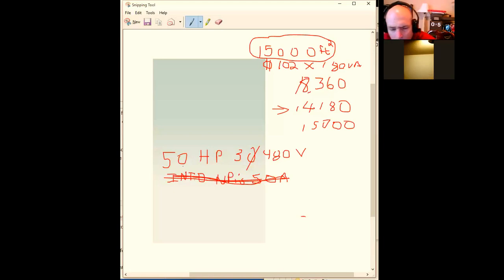Okay, what you got? I've got a fire pump motor that is a 50 horsepower, 480 volt, 3-phase motor used as a fire pump. And they're asking what size inverse time circuit breaker would you select to protect that fire pump. And the choices are going to be 500, 600, 400, and 800. So it's a 50 horsepower, 480 volt, 3-phase fire pump. Looking for an inverse time circuit breaker, an ITCB. Would it be a 500 amp, 600 amp, 400 amp, or 800 amp breaker?